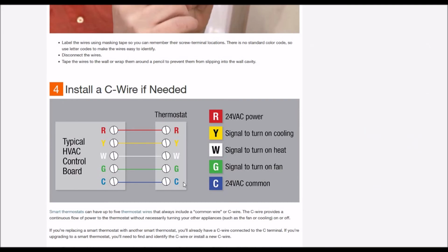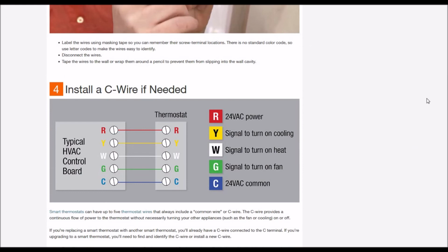And of course, be sure to check the batteries on the thermostat and be sure that it's not some old battery and not working properly. But once you're sure you've got 24 volts AC on the R and the C terminals, and you know you have a good battery, the thermostat may still be bad. So what you do is use a little jumper, and you jumper from R to W. When you do that, you'll bypass the thermostat, and the thermostat won't be involved anymore, because you just send 24 volts to the call to heat on W, which should turn on the furnace. So using a little jumper wire, just go from R to W and see if the furnace turns on. If the furnace does turn on, then you know you have a problem with the thermostat. If the furnace doesn't turn on, then something else is going on deeper, probably inside of the furnace itself, so you'll have to start going in that direction.